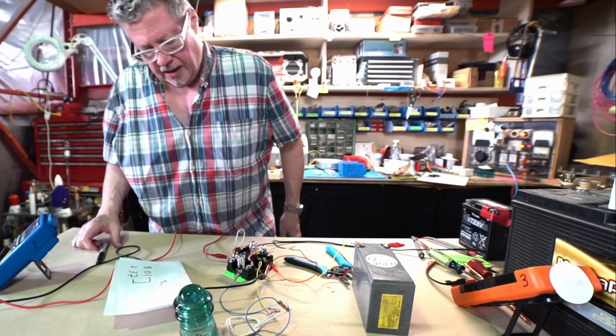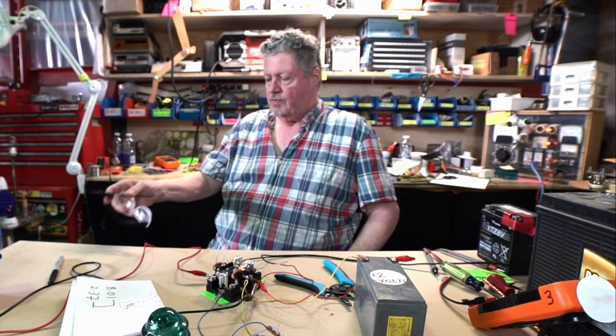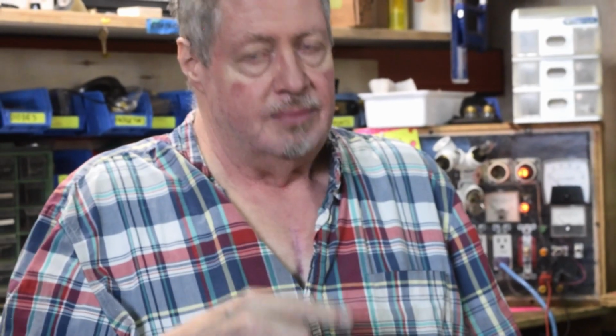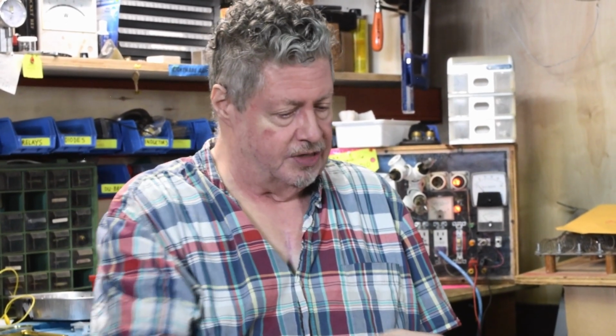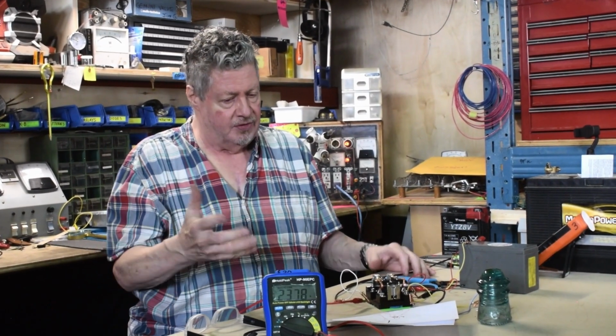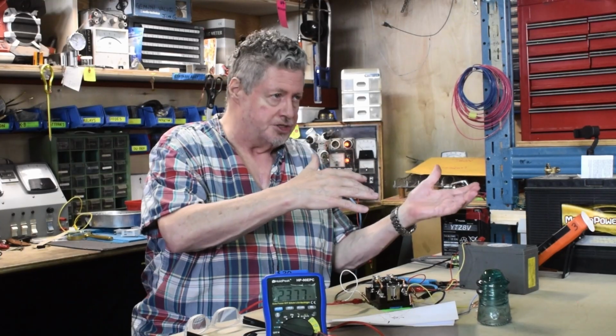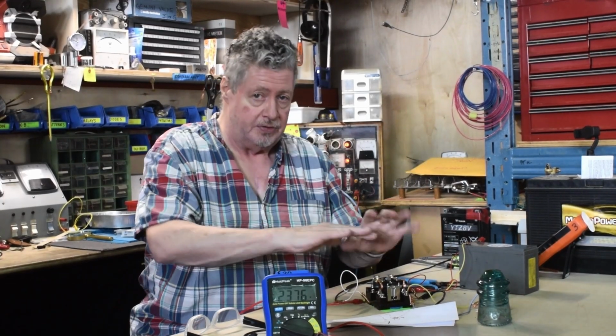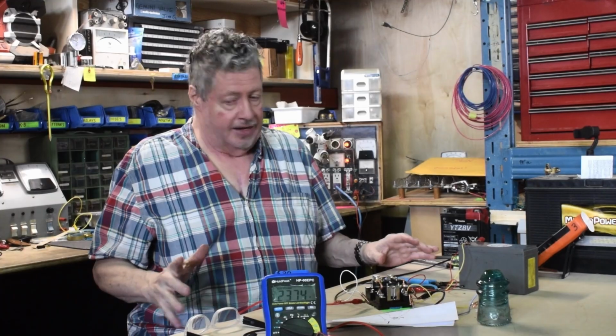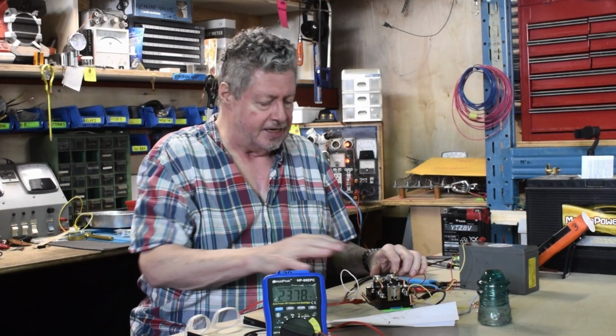This is valuable when you want to hook up a windmill and you want the windmill to have gained some speed before it's engaged with charging the batteries. So you're isolating the charging device, the generator, from the battery pack so that the generator, when idle, isn't drawing any power. The relay disconnects the two. As the windmill speeds up and voltage goes up, it'll kick in, and we're charging batteries. When the wind dies down, it drops out and they're isolated. That's the purpose of this relay in that type of setup.